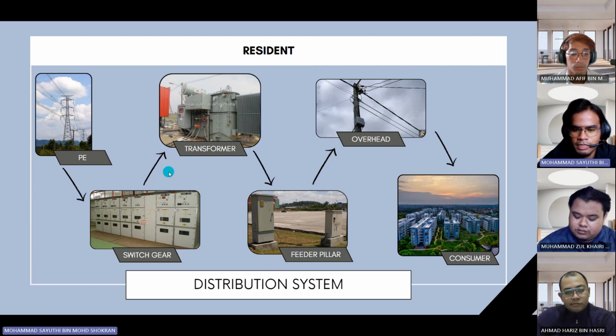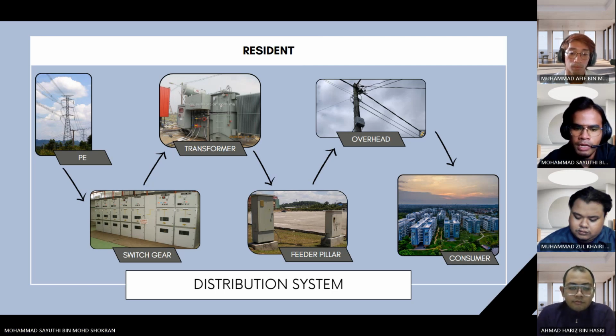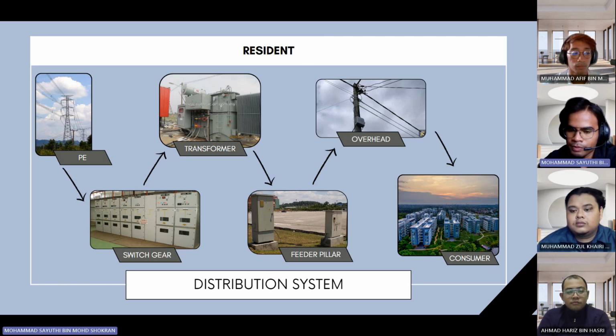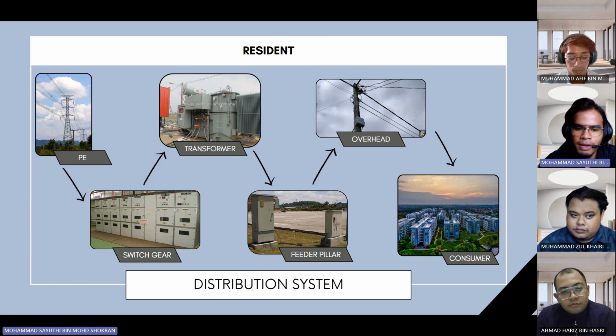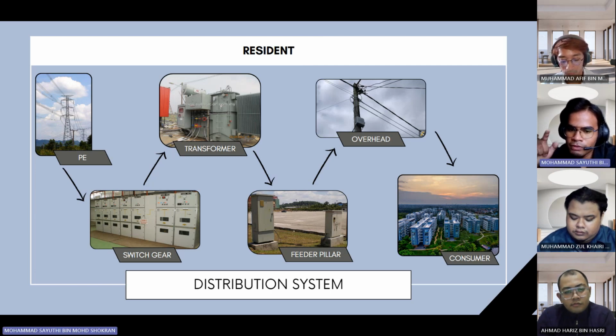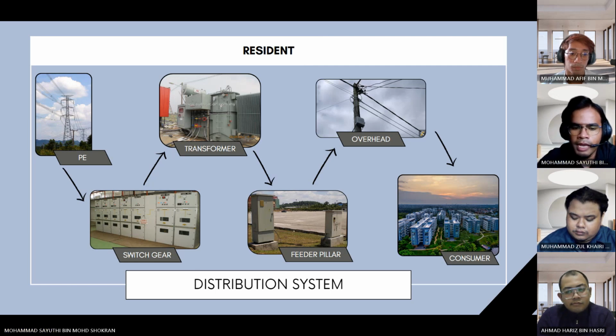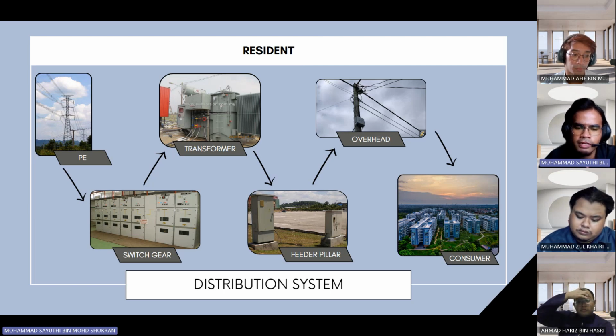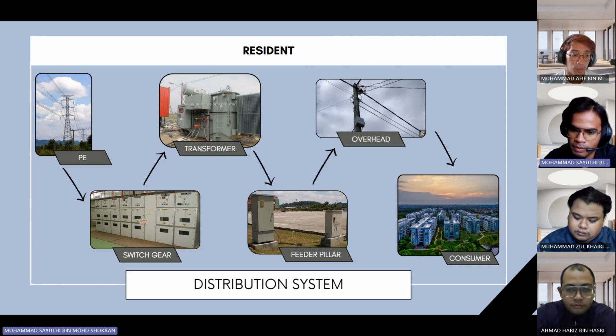for the electrical substation PE in residential areas, I suggest we use the switchgear distribution system, the RMU. Why? Because RMUs are primarily used in the distribution network to control and protect the flow of electrical power. They are commonly employed in ring main systems where power is distributed to multiple branches. RMUs are typically used for low to medium voltage applications, ranging from a few kilovolts up to around 36 kilovolts. The RMU generally has a lower breaking capacity compared to a VCB, vacuum circuit breaker. They are suitable for interrupting smaller fault currents typically encountered in distribution networks.